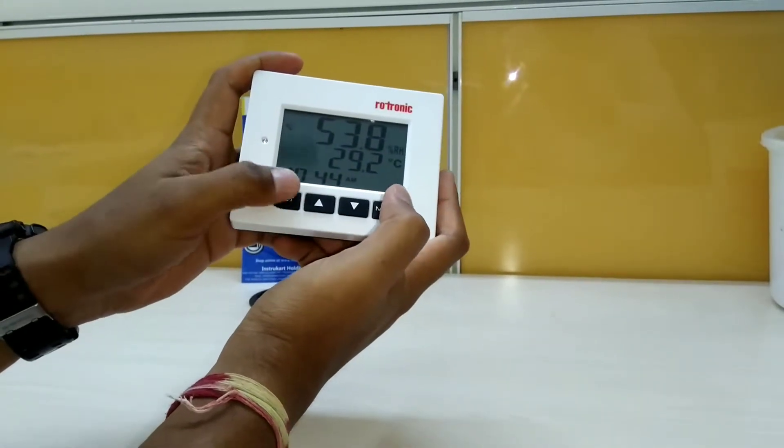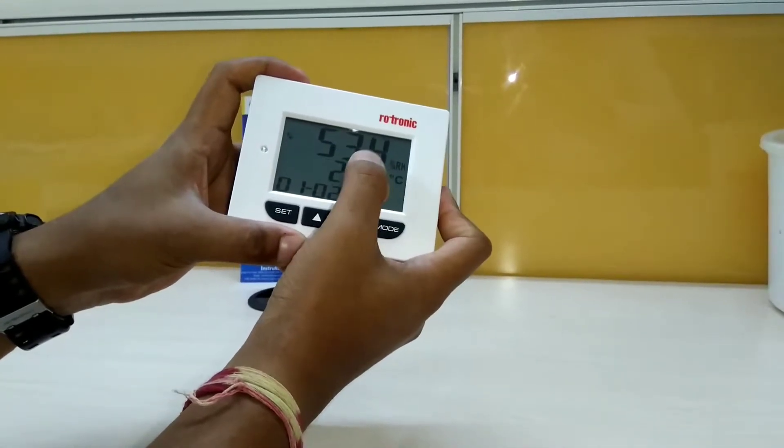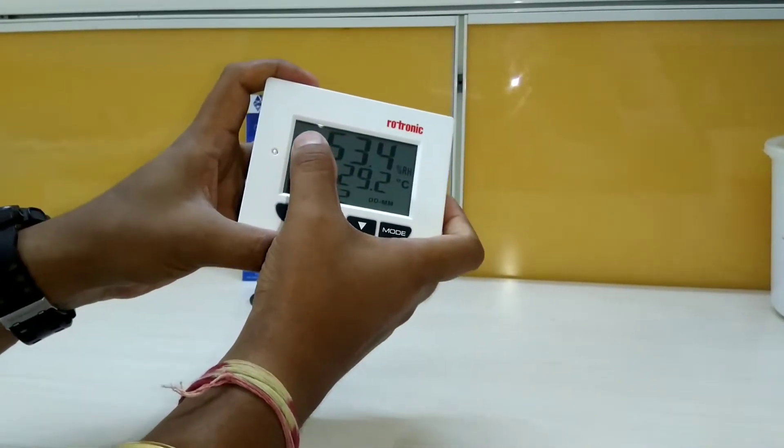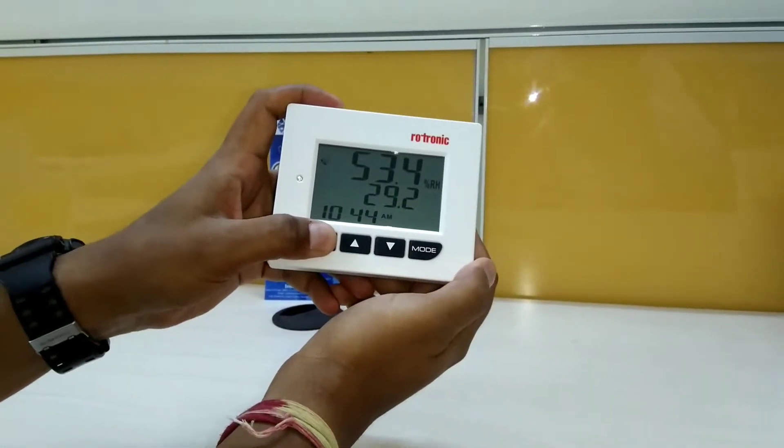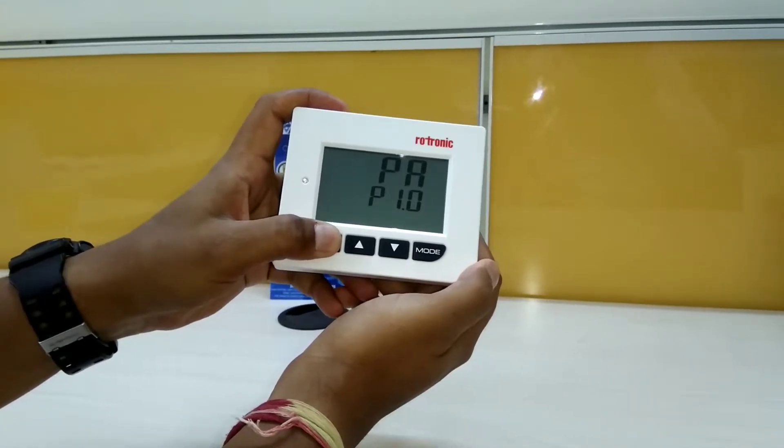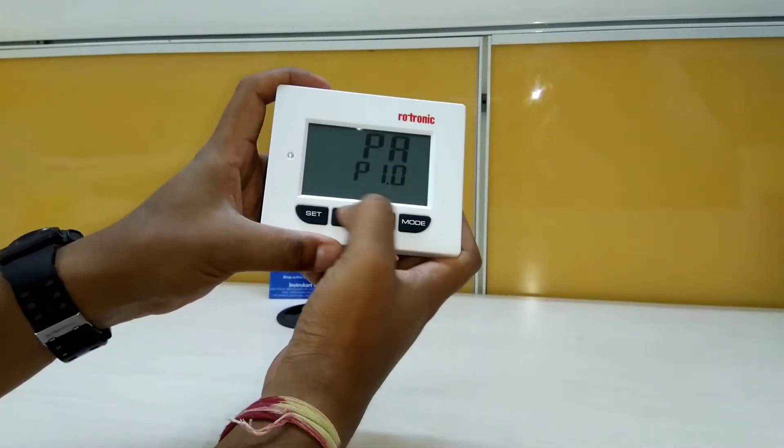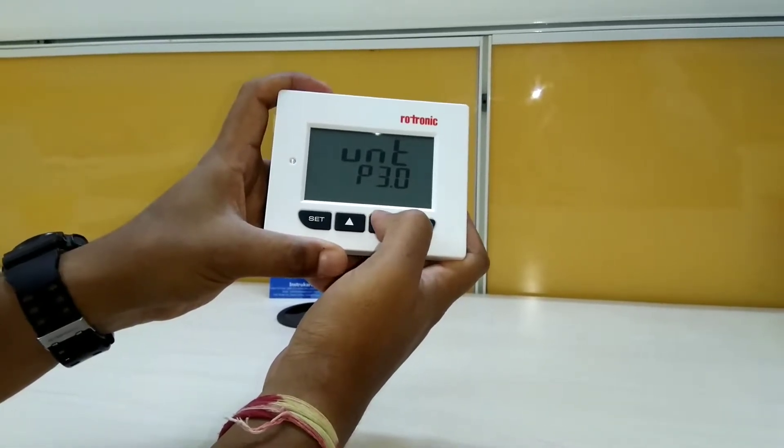We can use the set button to give a set point for high and low where it will give you an audio visual alarm. For this, you have to long press the set key and then use the up and down button to toggle between different modes.